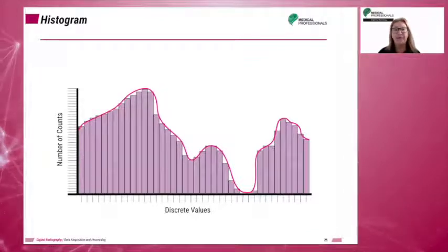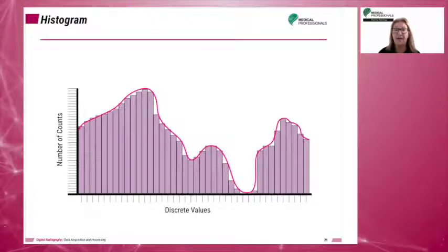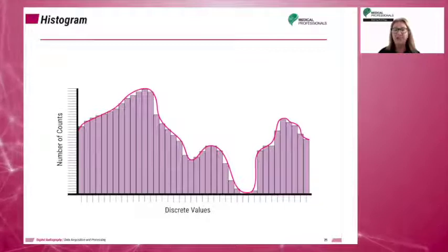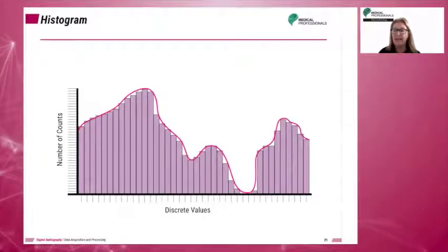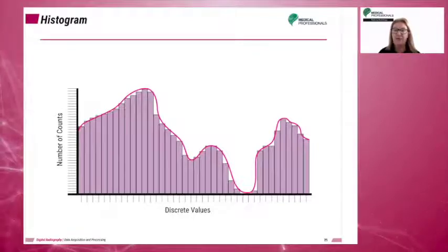Computer software will use processing algorithms to correct the image. In CR, after scanning of the entire PSP, the exposure field and edges of the image are identified. All exposures outside of the exposure field are excluded from the histogram and not displayed on the monitor. Histogram analysis errors are less common in digital radiography than in computed radiography, because image data in DR is extracted only for the exposed detectors, while in CR the entire plate is scanned to find the VOI.